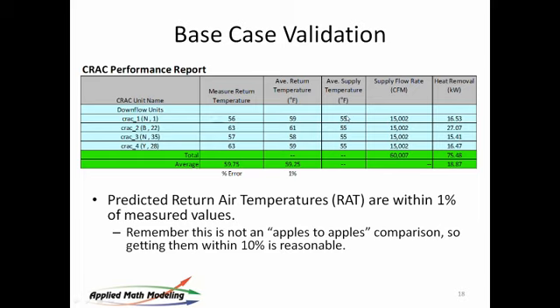You're correct, point that out. They look very cold, but this is where the client was operating. That's exactly right. When we did this analysis, they were operating at 55. The return temperatures were predicted to be 59, 61, 58, and 59, and the measurements are shown here. So the average error here is 1%. It came in quite nicely.